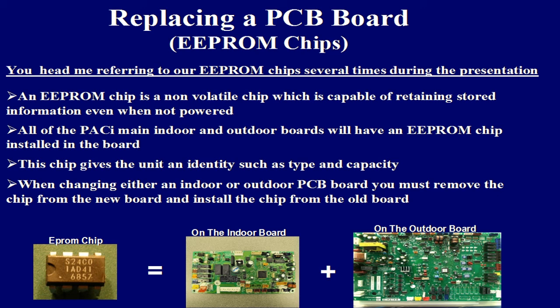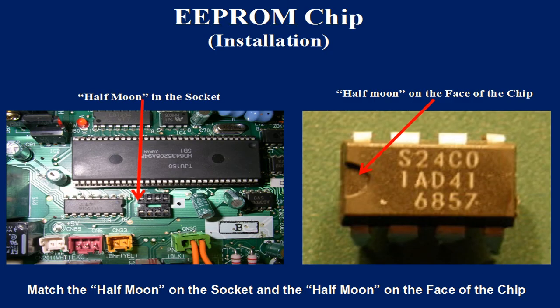A bent pin can be straightened back into place using care. Make sure all pins are seated properly into the socket on the board. This slide illustrates the half-moon notch on one end of the EEPROM chip and on the board socket. This marking on the EEPROM chip and the socket on the board should align when the chip is installed correctly. The system will fail to operate if the chip is installed backwards.